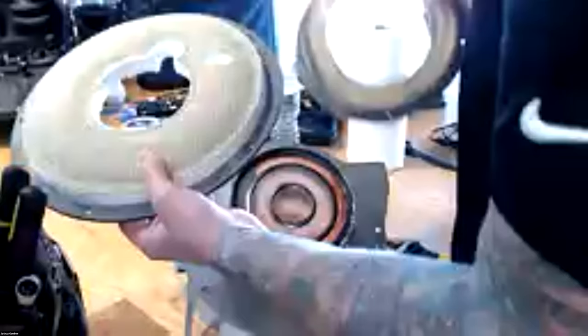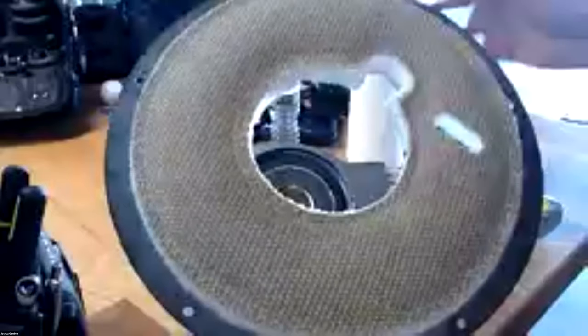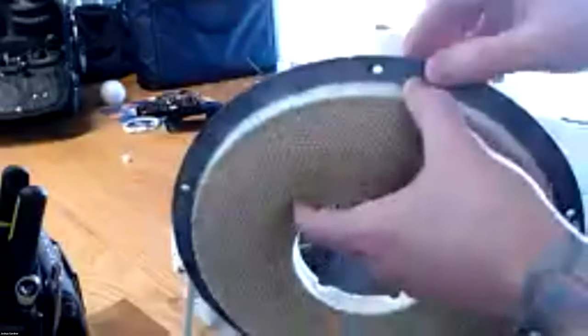I mean, both these kind of look fine. This one's obviously been on and off a bunch of times, but if we see overheating, we'll see a lot of discoloration through here. And then also we want to inspect and make sure our gasket's good. If you have any deforming, cracking, or you removed it and damaged it, obviously we want to replace that. But when we take this off or we replace it, we do replace it.